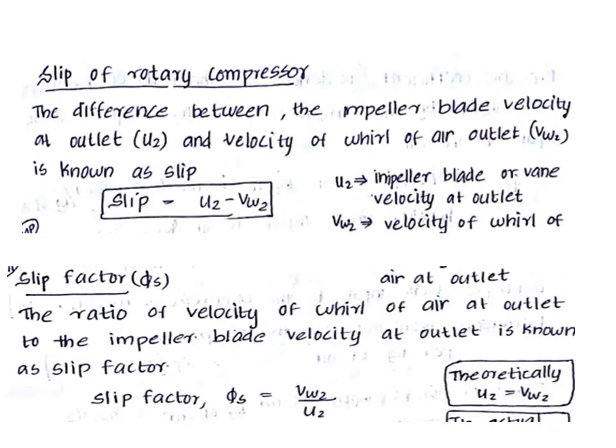We are learning about the centrifugal compressor. In this video, we have a numerical problem solving the centrifugal compressor. This is the slip of the centrifugal compressor. Slip is the difference between impeller blade velocity U2 and the whirl velocity at the outlet, VW2. Slip is equal to U2 minus VW2.